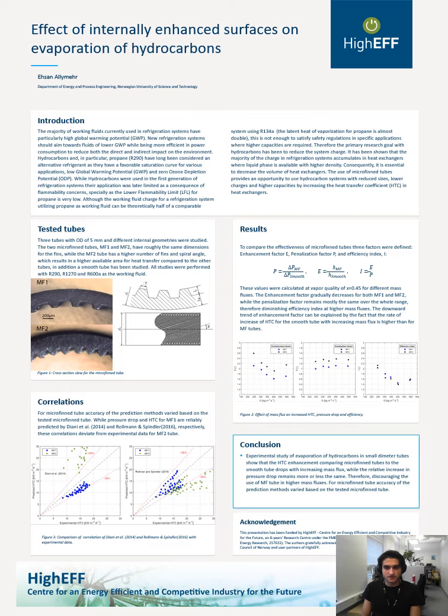Hi, I'm Ehsan Allymehr, and today I want to present my work on the effect of enhanced surfaces on evaporation of hydrocarbons. What we have been working on here has been a part of the push for a more widespread adoption of natural working fluids in heat pump systems, and hydrocarbon is a part of this fourth generation natural refrigerants. The systems with hydrocarbons are usually more focused on small-scale systems, and the major challenge with the hydrocarbons has been the low allowable charge in systems because of the flammability concerns.